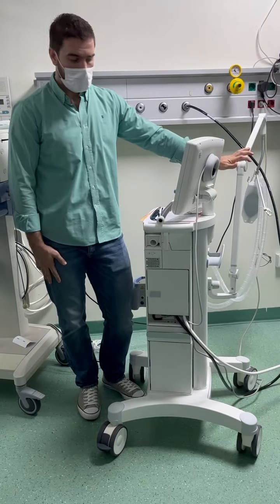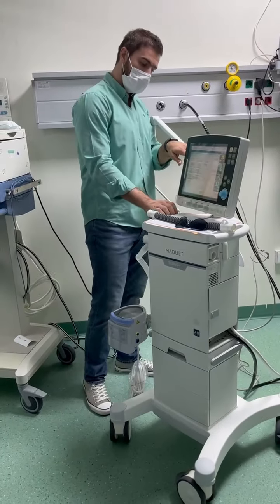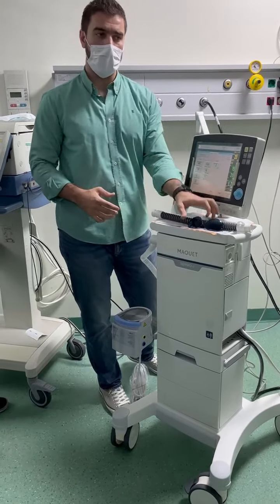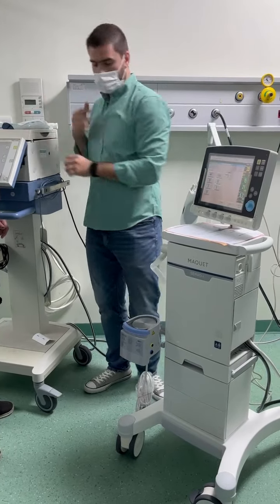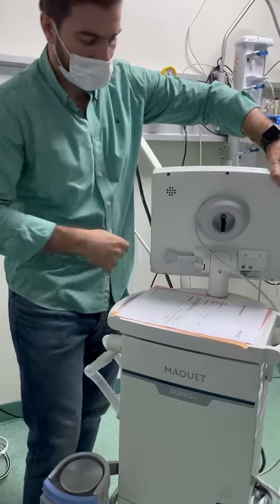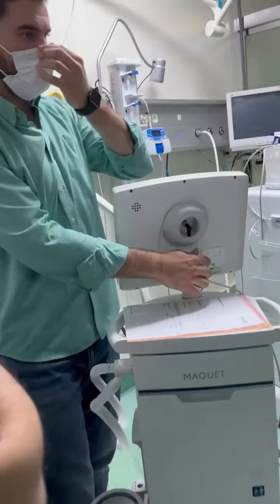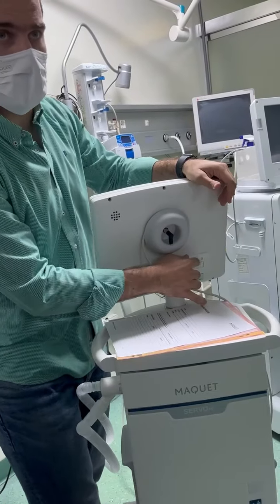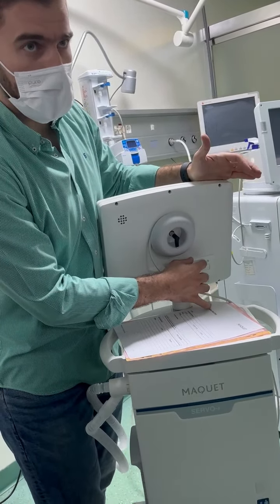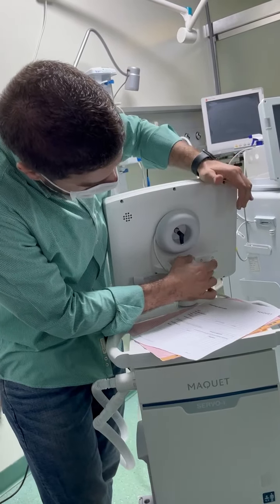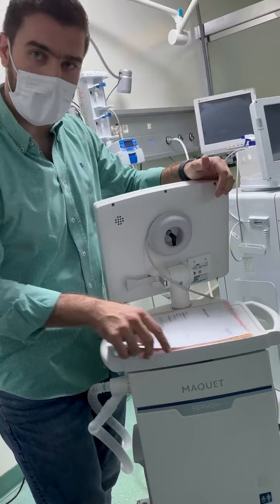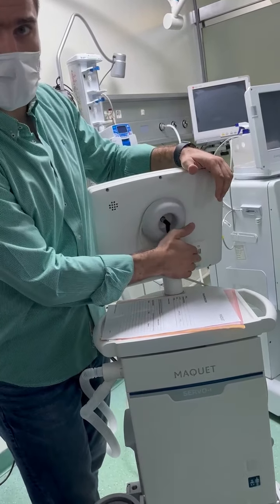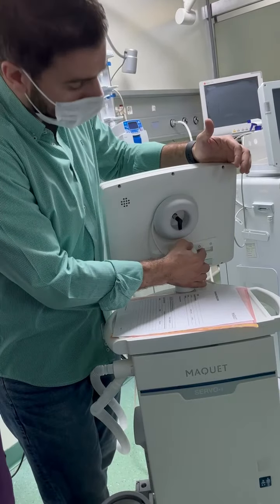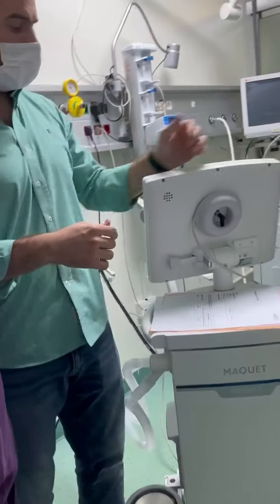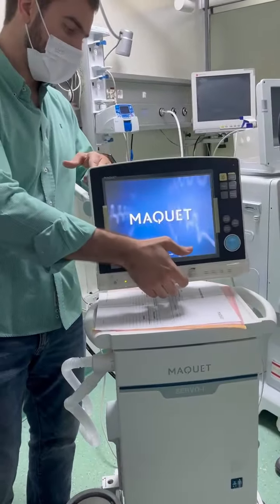Very simple. Right. The second part of my presentation will be the pre-use check. How to do a pre-use check and why do we need to do a pre-use check? First of all, how to switch the machine on and off. Can you see this small gate? Now the machine is on. As long as it is on, the gate will be closed. Okay. In order to switch it off, you have to take it down and take this one to the side. For safety. When it is switched off, the gate will be locked. How to switch it on? Take it to the right and leave it, and the door will close automatically. Okay. After we start the ventilator, alright.